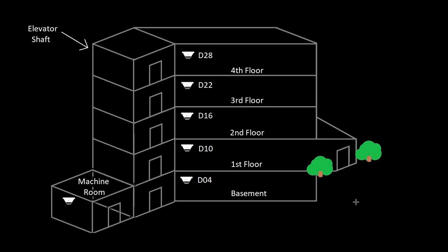Okay, so where I left off in the last video I was starting to explain how if the machine room were located in the basement, you would send the car up to the first floor and you would flash the hat. Now depending on which elevator company you're working with, you're either going to be turning on just the fire hat flash relay when you do that, or you're going to be turning on primary recall to send the car to one and fire hat flash to flash the hat.